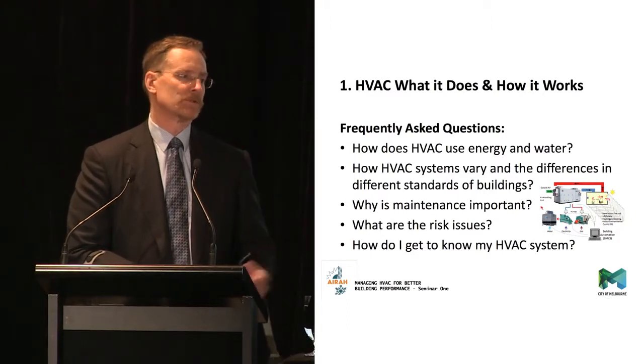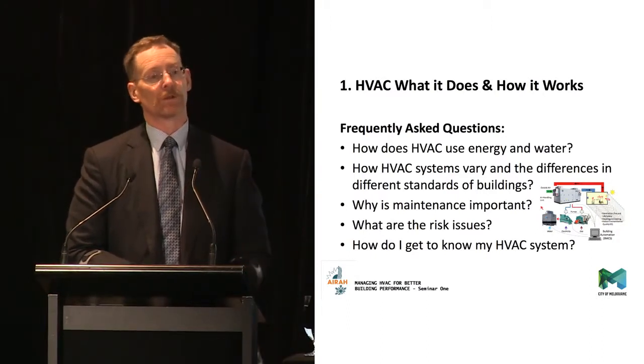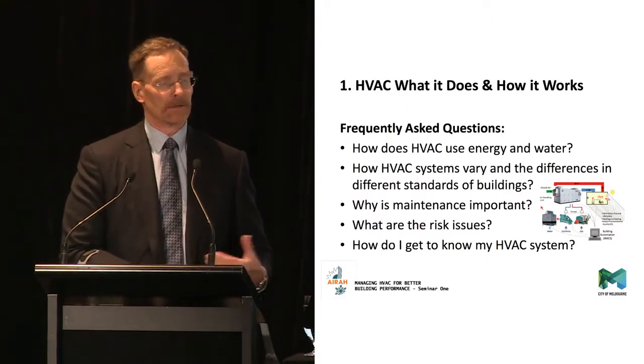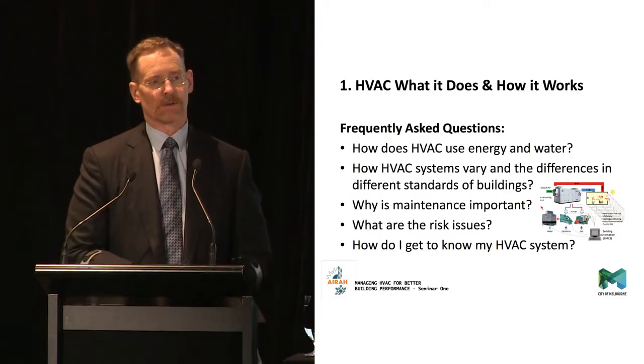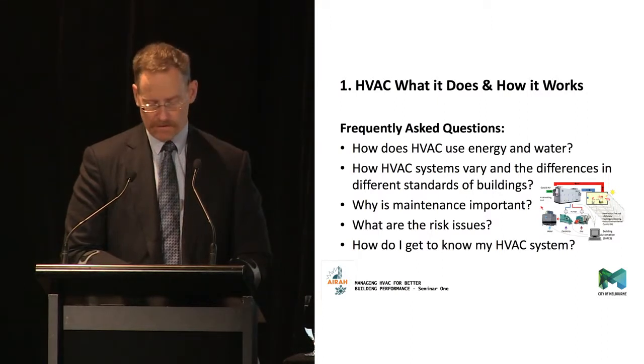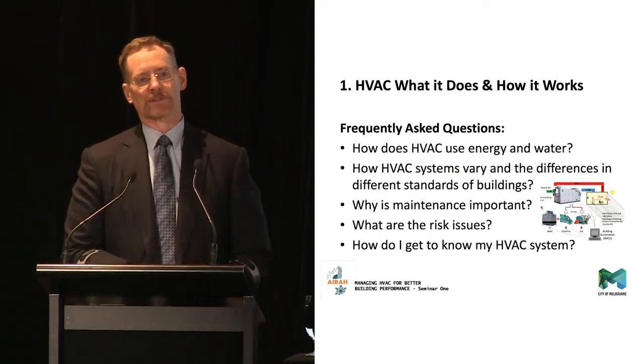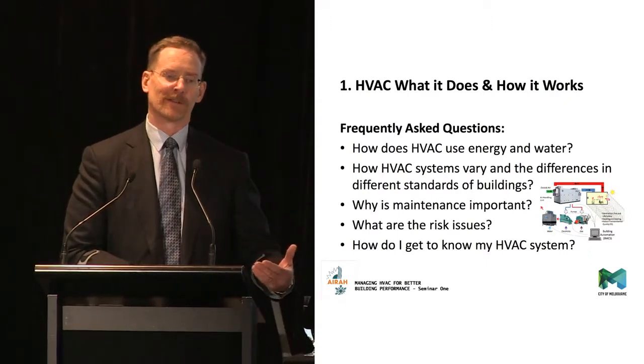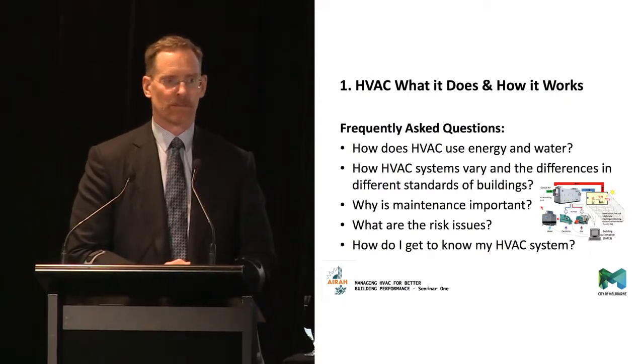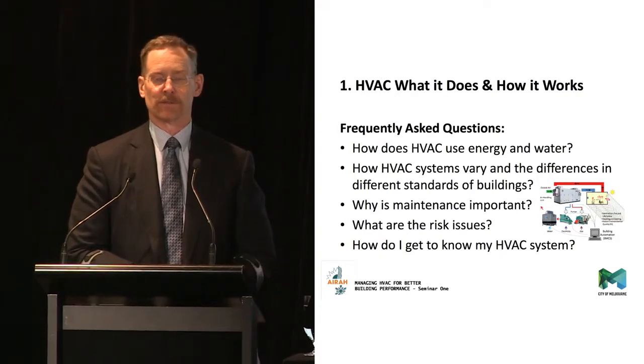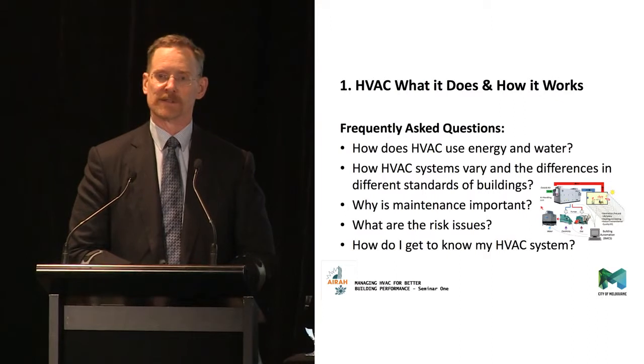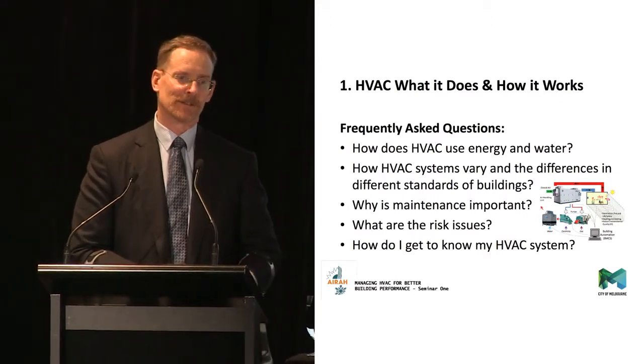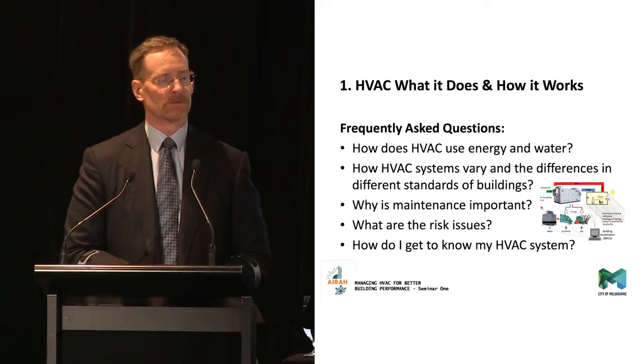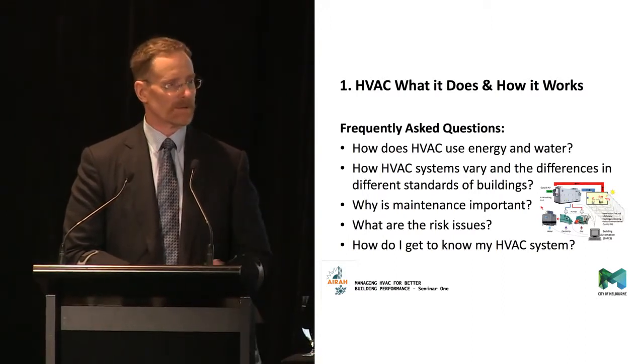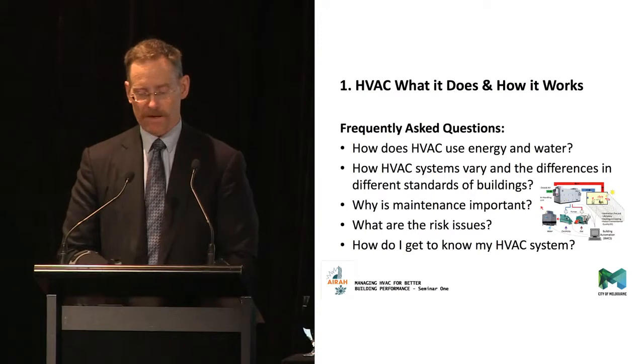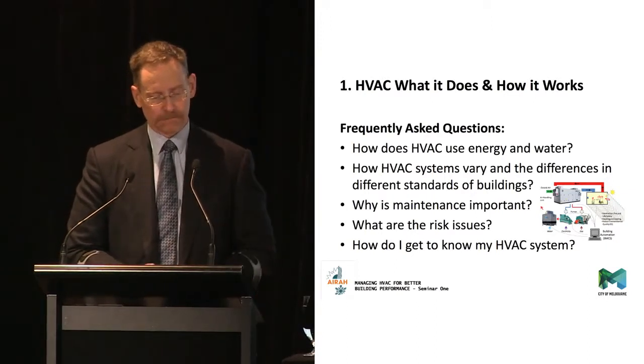From a water perspective, water is used in cooling towers through evaporation, but there's also a lot used in drainage, keeping concentration of solids down, and keeping the system clean. Interestingly, water consumption in a cooling tower is very much proportional to how much energy you're trying to push out of the building, so it's affected by energy efficiency. The more energy efficient a building is, the less energy you need to push out, so the less water you use. Improving energy efficiency also improves water consumption - the two are very hardwired together.